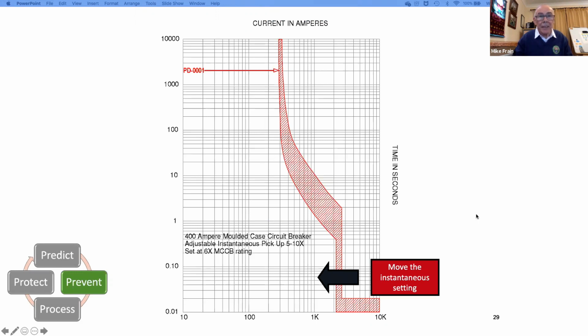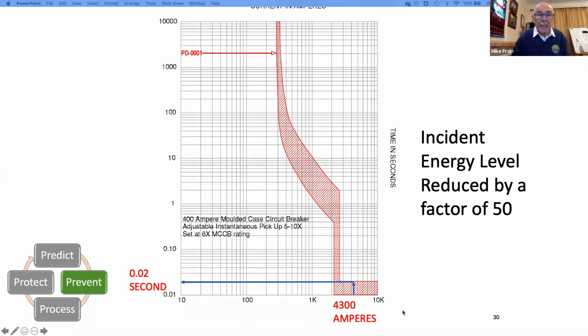The next slide, I'm suggesting we can start to think about lowering the incident energy level, because as I'd said earlier, if we lower the time to trip by a half, we'll actually lower the incident energy level by a half. And in this case, we're going to move the magnetic protection settings over to 6 times rather than 10 times. So in the next slide, you can see that the same current of 4,300 amps has resulted in 0.02 seconds disconnection. So rapidly, instantaneously, in other words, the fault is going to be disconnected. So actually, by the action of a twist of a screwdriver, we just lowered the incident energy level by a massive 50 times.